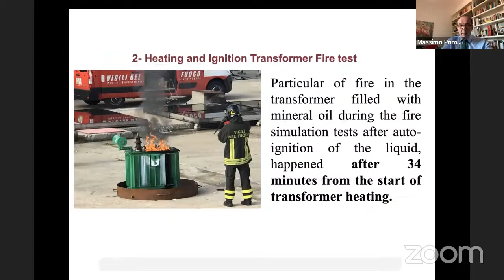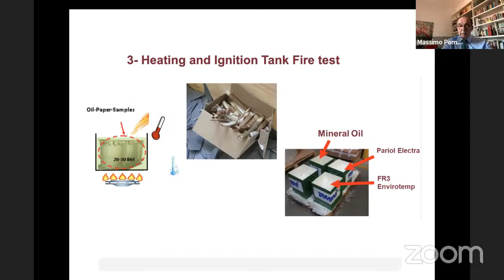Then we also made different tests in an open vessel, so more contact with air, making the fire easier. And we had identical results: better fire behavior and better fire performance of the natural ester transformer compared with the mineral oil distribution transformer. Okay, this video is going on. The left side is mineral oil.